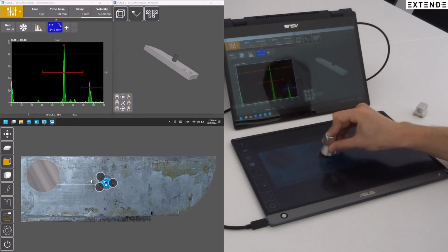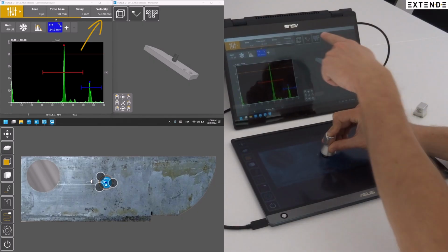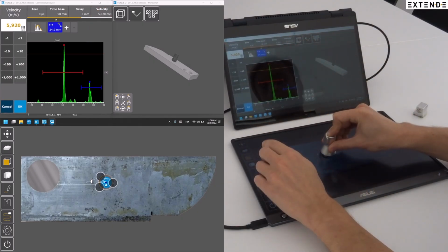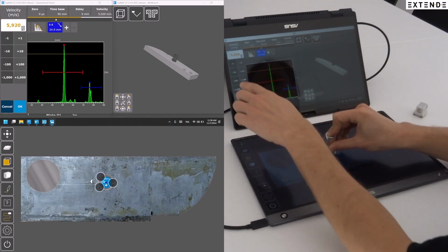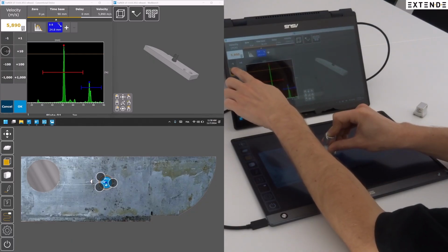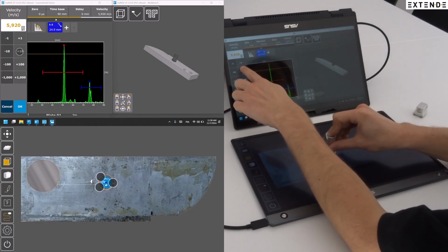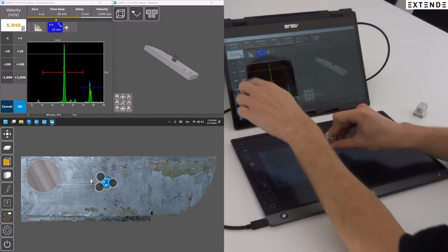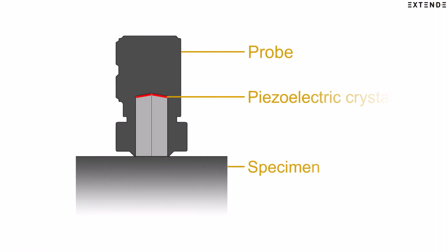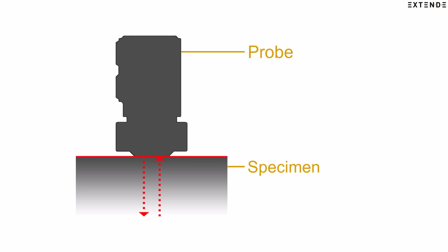You must now go to the Calibration category and set the velocity iteratively to measure the 25 mm corresponding to the thickness of the V1 block. Once velocity is calibrated, you can calibrate the zero. It eliminates the wave's travel time from the transmitting element of the probe to the surface of the inspected specimen. It then allows you to perform the measurement from the inspected surface rather than from the piezoelectric crystal.